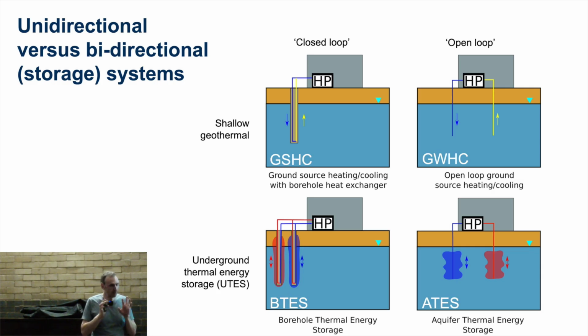But what would be neater? I said that in the summer, we're injecting back into the aquifer waste heat. And in the winter, we're injecting back into the aquifer waste cool. What if we reuse that? So instead of just leaving it in the aquifer, what if I store heat in the summer and produce that back out of the aquifer in the winter, and then store that waste cool in the aquifer and bring it back out in the summer? That's exactly what we do in underground thermal energy storage.